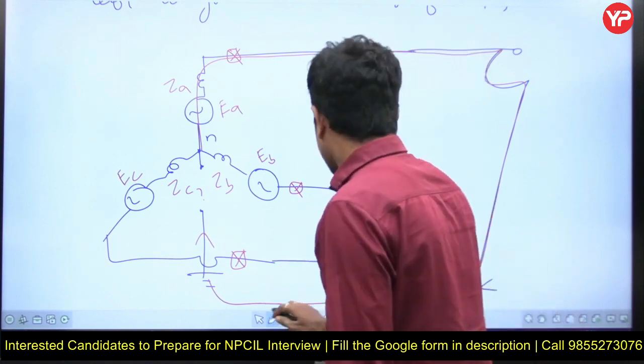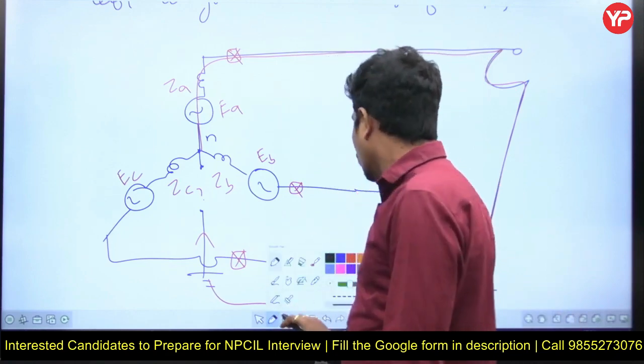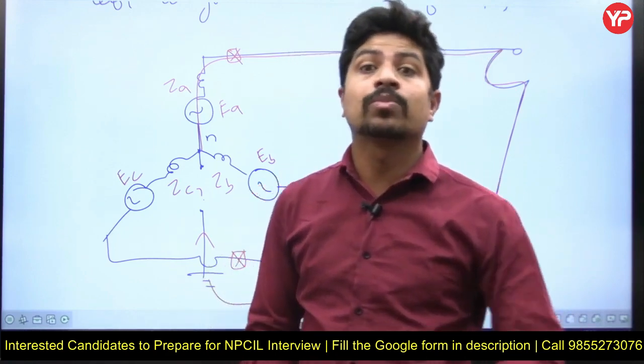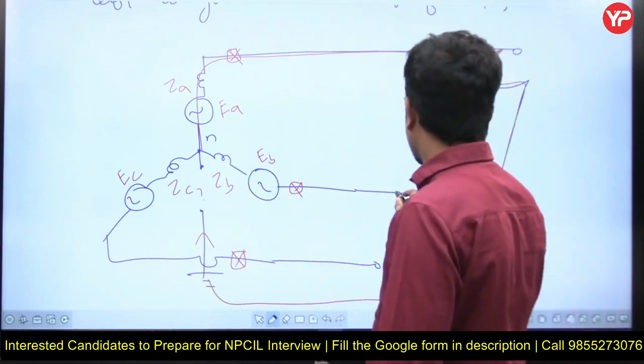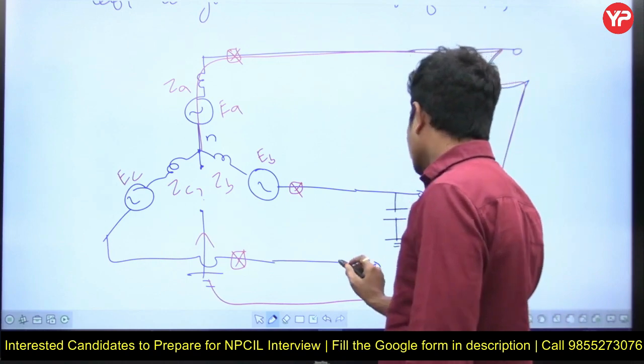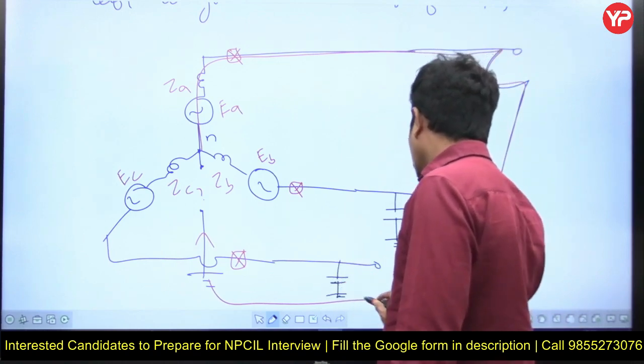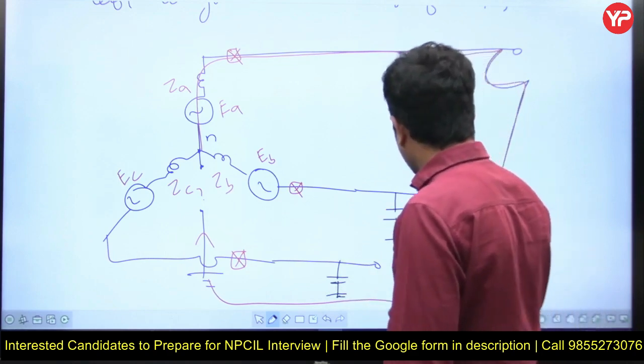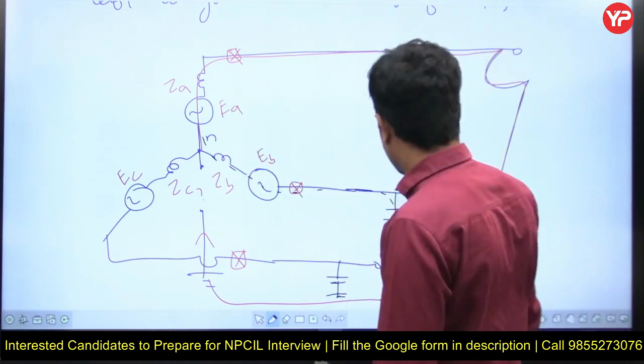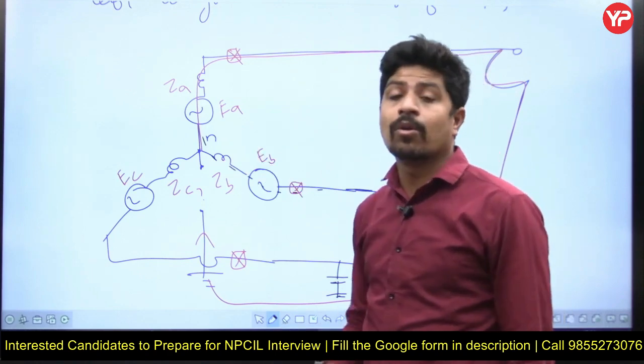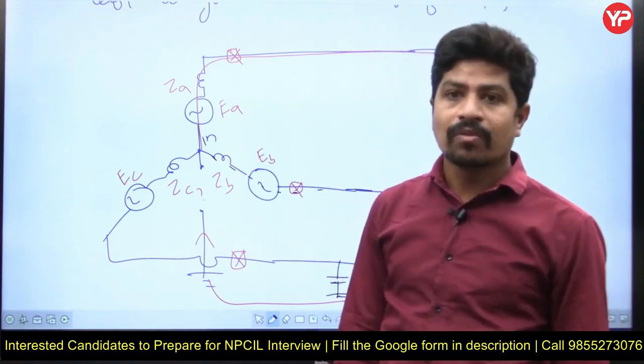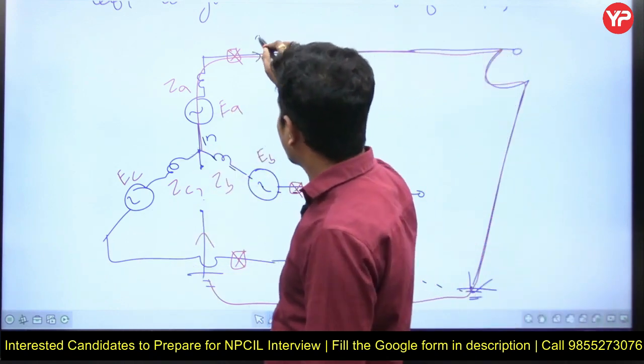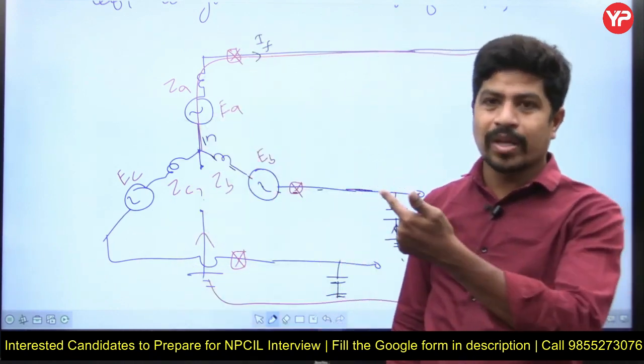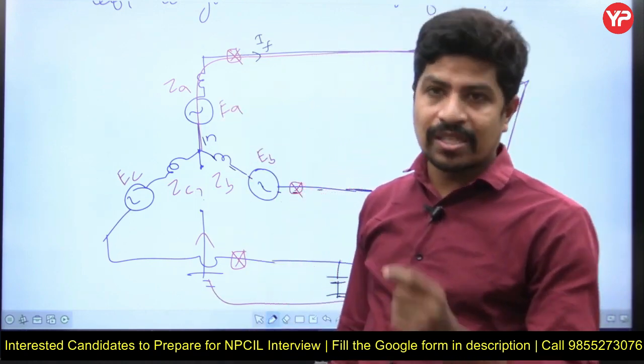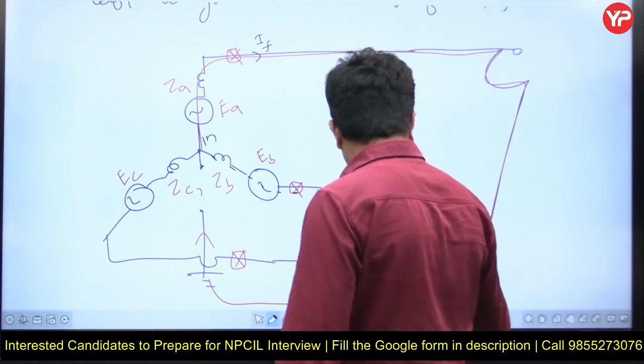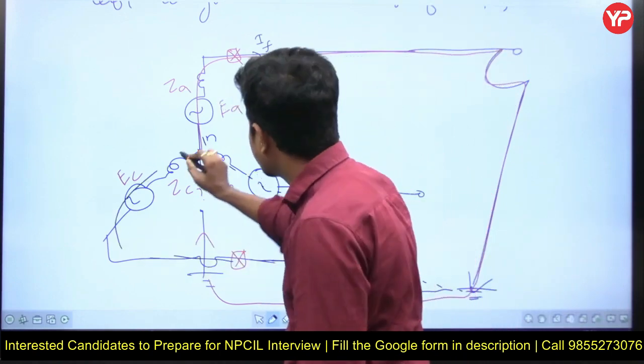Another disadvantage is that a small amount of fault current will flow. Then you may ask, sir, where is the closed path for the flow of that small amount of fault current? You know, there is capacitance which is formed to the ground. So the fault current makes a closed path through these phases, but this capacitive current is very small because it's not conduction current, it is displacement current. The fault current IF is flowing, but a very small amount. The relay and circuit breaker cannot recognize that condition as a fault condition. The small current makes a closed path this way also.